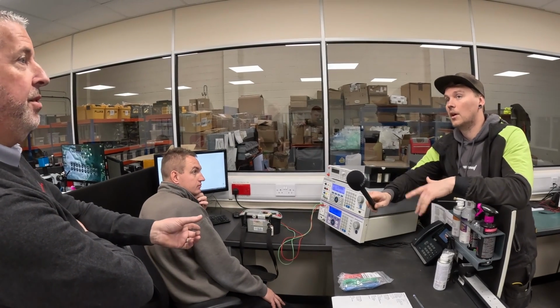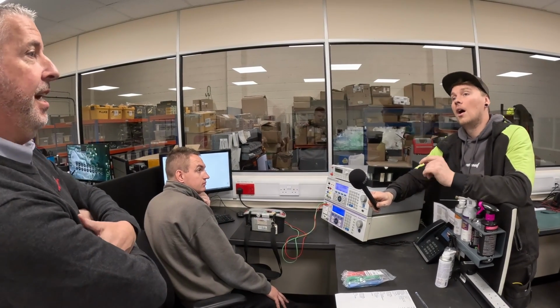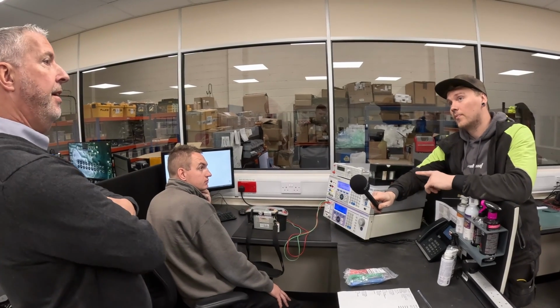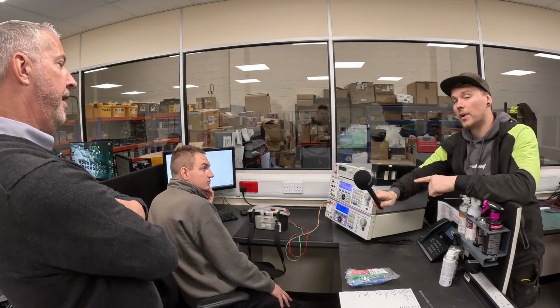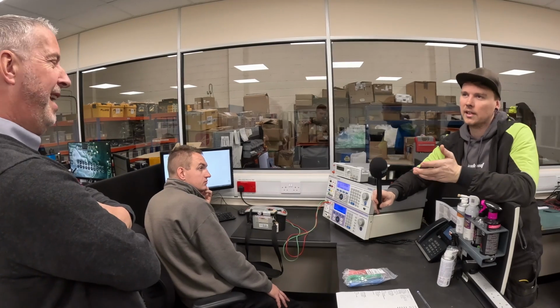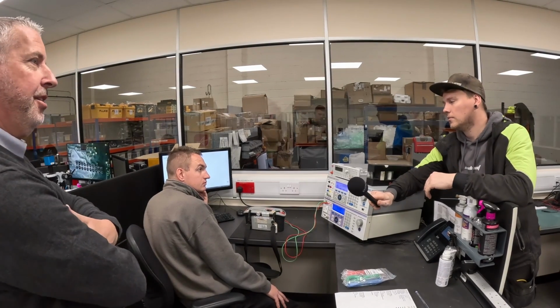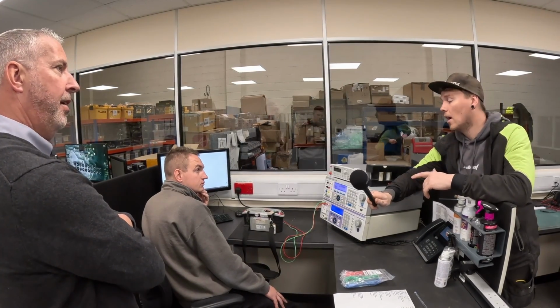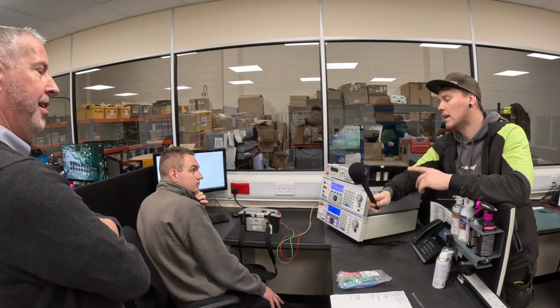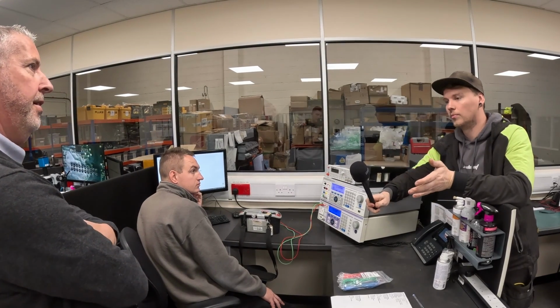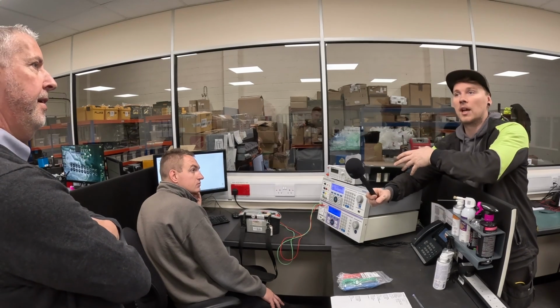That one can't - some of the newer ones now are doing a pre-insulation test. So that one will detect it. That would damage it then, because I did do it and it didn't seem to damage it, but I might have just got lucky. I think the recommendation is to drop it down to 250 volts if you've got an EICR type condition. A few people did say their testers can figure out that there's something on the line, so it won't push the full voltage through - it's basically doing a pre-insulation test.